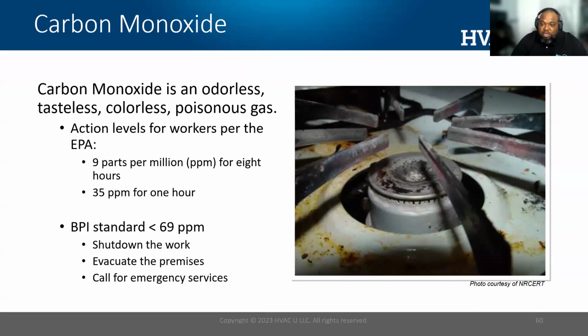Locally in my town here in Michigan, firefighters go on self-contained breathing apparatuses at any instance over 35 parts per million. So work with your local community or business organization to identify your procedures. BPI, the Building Performance Institute, has a standard, and they say that anytime the ambient CO level exceeds 69 parts per million, you need to shut down your work, evacuate the premises, and call for emergency services.